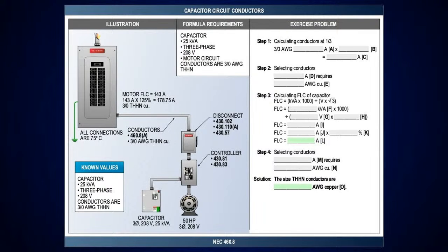You'll see from where the controller is, we have one of the new capacitor units in there. These are actually a digital type capacitor assembly, and it digitally reads everything. Okay. Nice. And this here is the same calculation. I've got 25 kVA capacitors, three-phase, 208 volts, and we're also telling you the conductors for the motor circuit are 3-aught. Okay. All you're going to do is the same calculation.